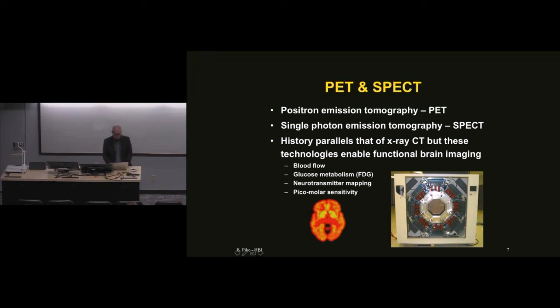That's the cover of a modern head-only PET scanner, where you see this whole ring of detectors around here. In the case of positron emission tomography, you have a radioisotope that decays by the emission of a positron. A positron is a positively charged electron. It's the antimatter of an electron. As soon as it's emitted, it's attracted to a surrounding electron. So positron and electron collide and annihilate and produce energy that's always the exact same energy, 511 kiloelectron volt gamma rays, which is given by Einstein's equation about the relationship between energy and mass. You get these two gamma rays that shoot out, and they're detected simultaneously by these detectors.